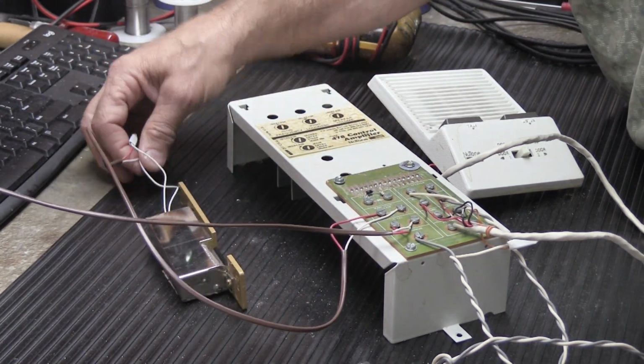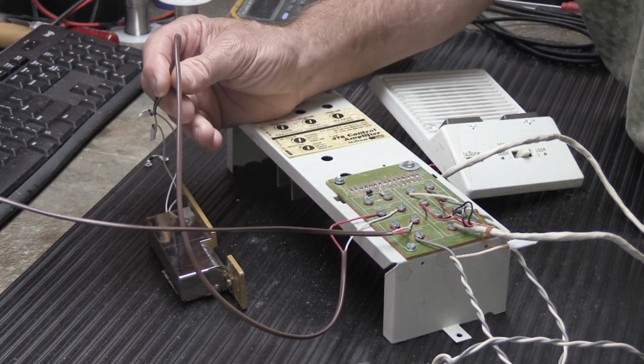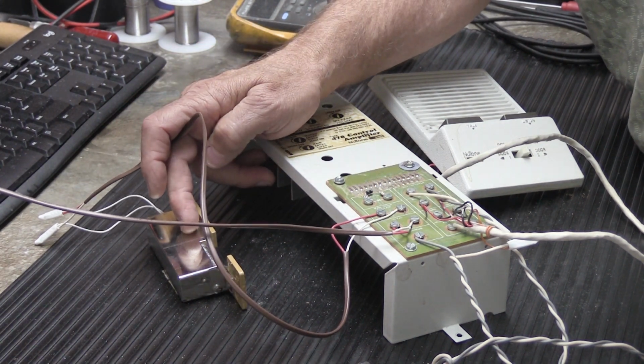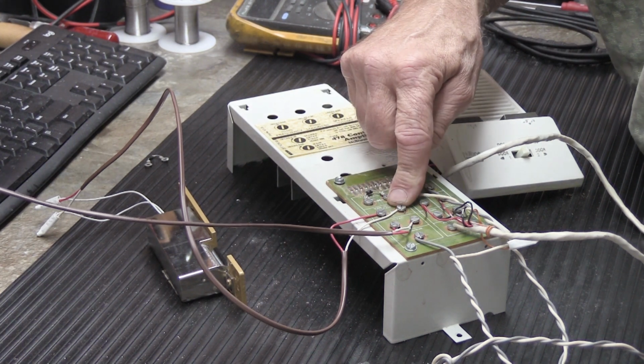There's a pair of wires here. You can see it here. It has a red and a white wire. Inside it's 18 gauge wire because it's powering an electromagnet in the door release. These 2 wires run back to the terminals on the control amplifier.